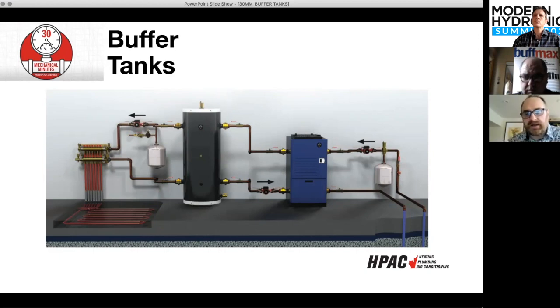It's going up and down. And I've got an appliance on the other side. In the old days, I had an appliance that basically could be on or off. It made heat at one rate. So if it was a 100,000 BTU boiler, it only made heat at 100,000 BTUs. Now we have modulation, which is a big improvement. So I can try to modulate, and match how much heat I'm making to how much heat my system's taking out. Well, that sounds like a great solution, and it works quite well, but it's complicated. How does my boiler know that? And so we do outdoor reset, and we try to guess at that. And that's great. But again, my boiler comes on, it's trying to match that load, and my heat load is always changing. It's like a moving target. So it's very difficult to get an appliance that can keep up with that.